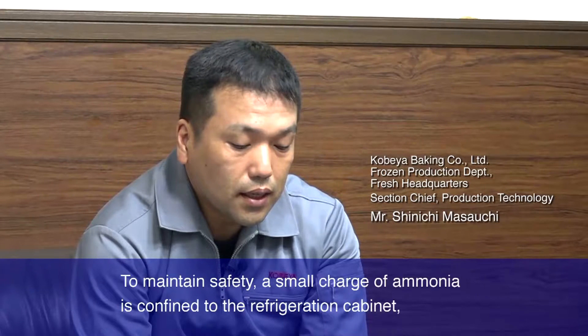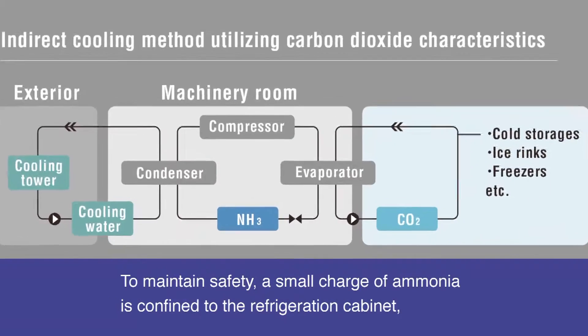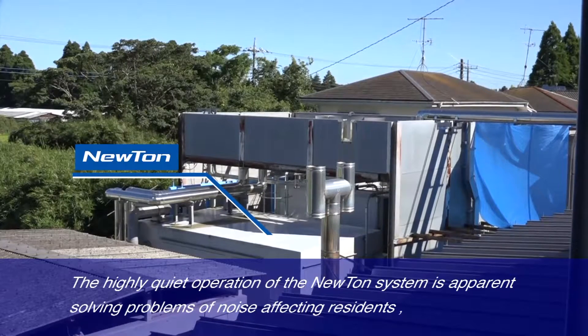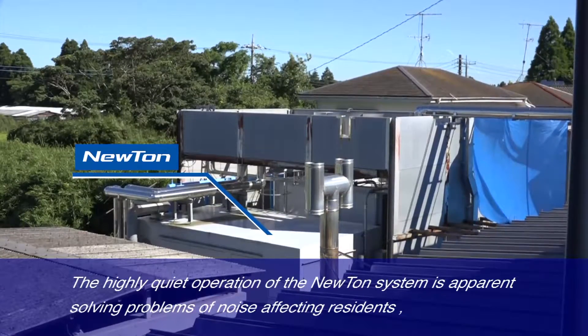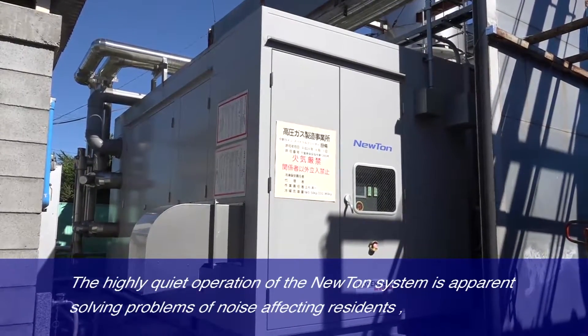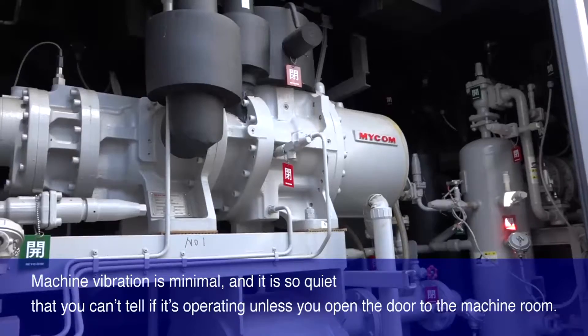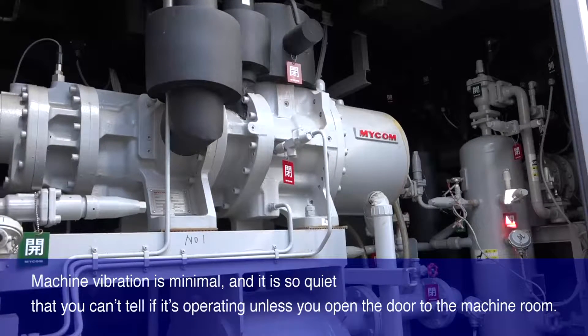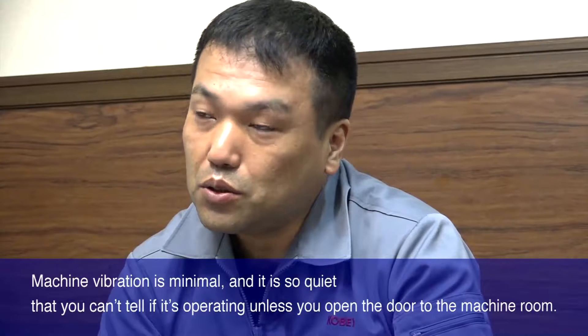To maintain safety, a small charge of ammonia is confined to the refrigeration cabinet, reducing the risk of leaking out of the equipment. The highly quiet operation of the Newton system is apparent, solving problems of noise affecting nearby residents, allowing it to be stored on the ground floor instead of the second floor. Machine vibration is minimal, and it's so quiet that you can't tell if it's operating unless you open the door to the machine room.